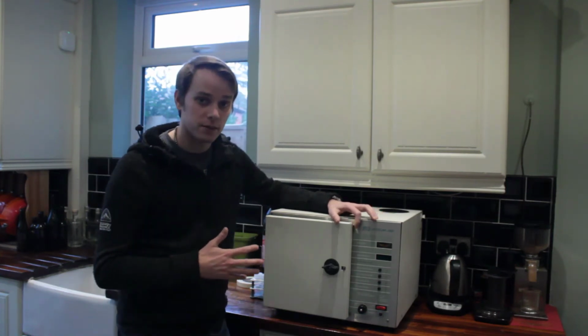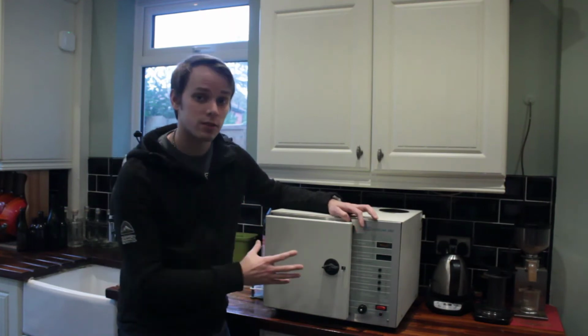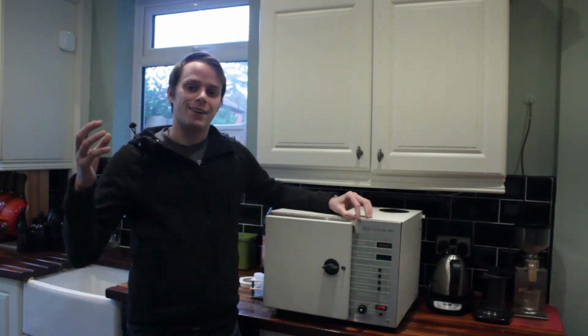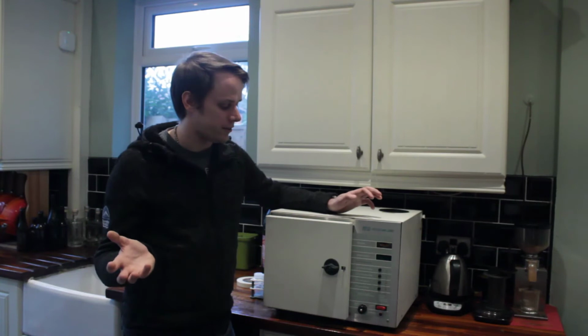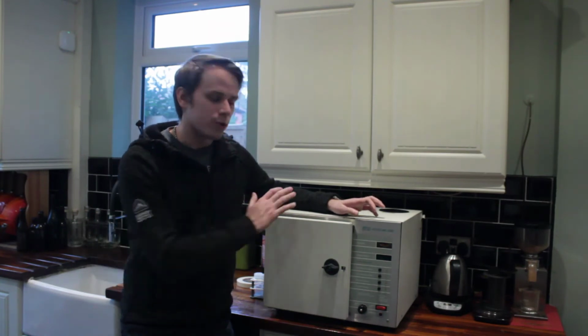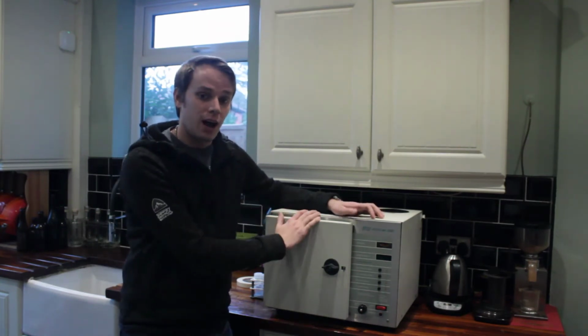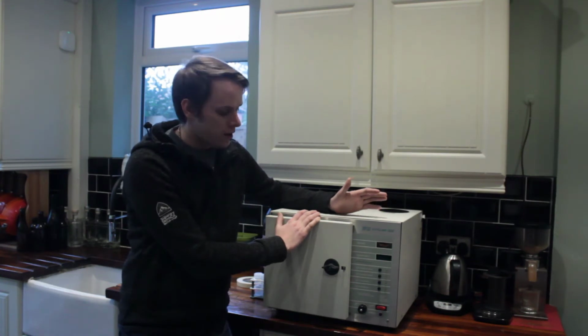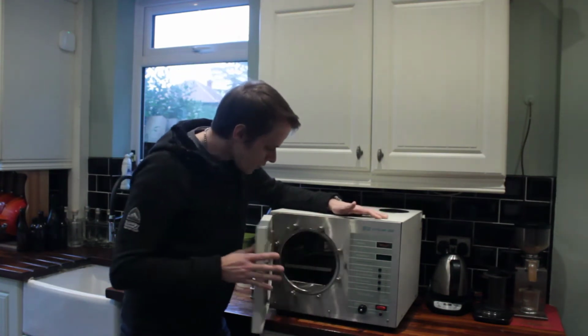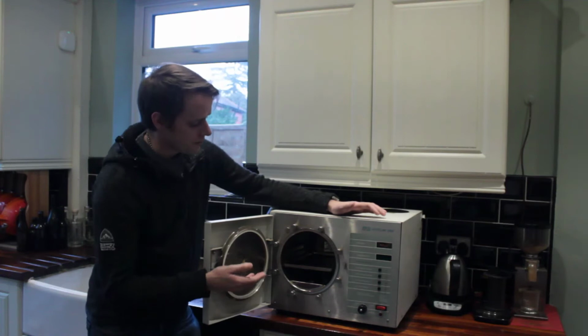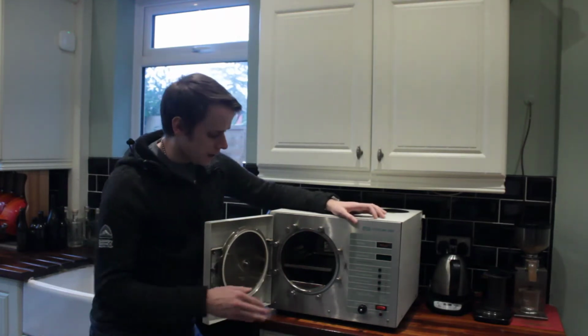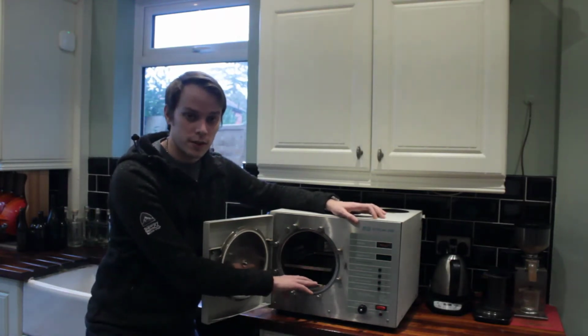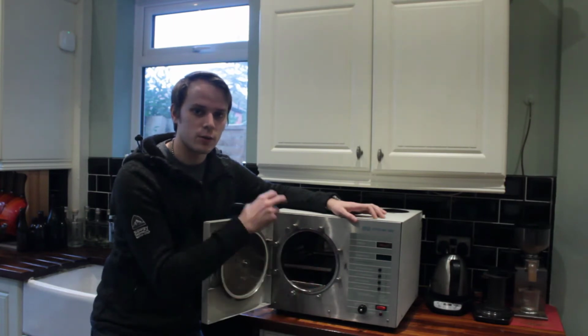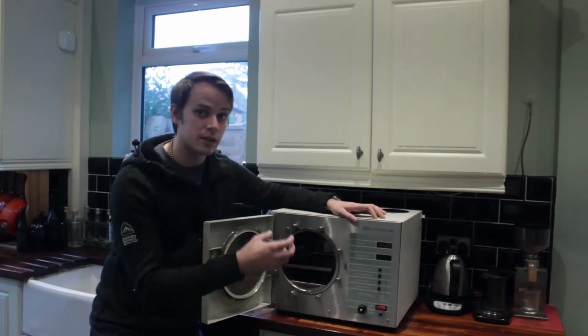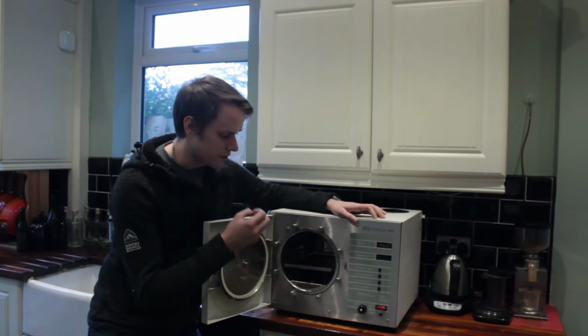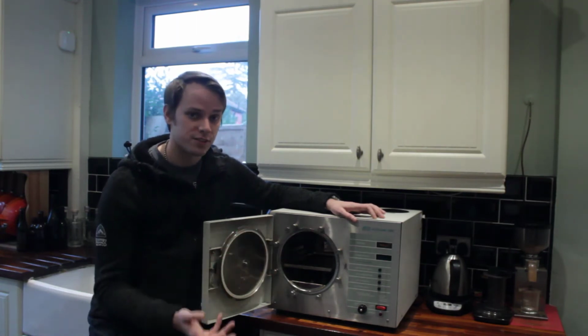So I'm going to talk a bit about this machine so that if you find one of these, you can use it yourself, you know what the different bits do. But we'll also have a general overview of what an autoclave is. So first off, we've got the chamber. Now this is a pressure vessel. We've got a heating element in the bottom to get the water up to temperature, create steam, create pressure. We've got various valves for allowing water in and steam out.